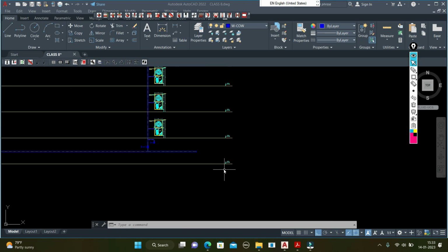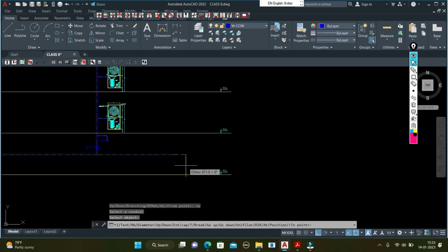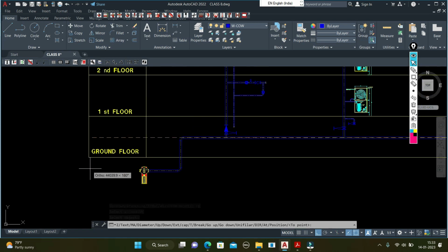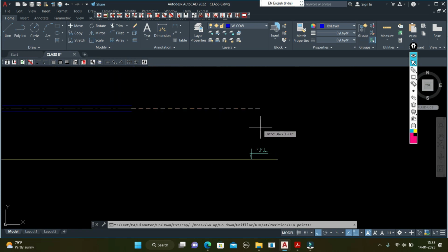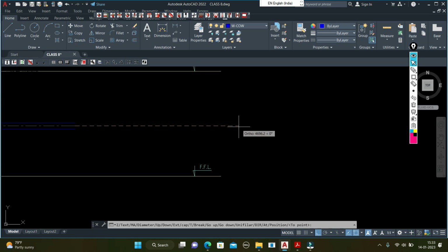Here also this is the breaching inlet. We can also connect to the breaching inlet, because breaching inlet is very important for the civil defense. Okay, this is the ground level, right? This is the ground level. So from the ground level, the breaching inlet distance should be 457 to 1219 mm. Between these, the breaching inlet should be. I already explained in previous video. You will watch that one. Okay.